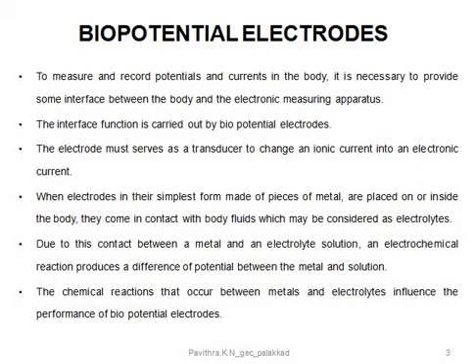They need to be kept in contact with the body in order to detect the body potential. In this case, we are considering the body fluids as electrolytes. Due to the contact between this metal piece and the electrolyte solution, there will be an electrochemical reaction that will produce a difference of potential between the metal and the solution.